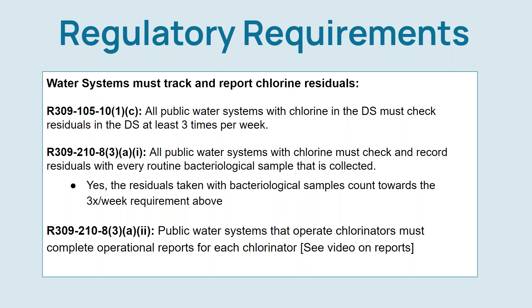Let's begin by quickly going over the regulations. First, R309-105 requires all water systems with chlorine in the distribution systems to check and record free chlorine residuals at least three times per week. Second, R309-210 requires systems with chlorine to measure and record the free chlorine residual with every routine bacteriological sample. The chlorine residuals taken with the bacteriological samples can be used to satisfy the three residuals per week requirement.